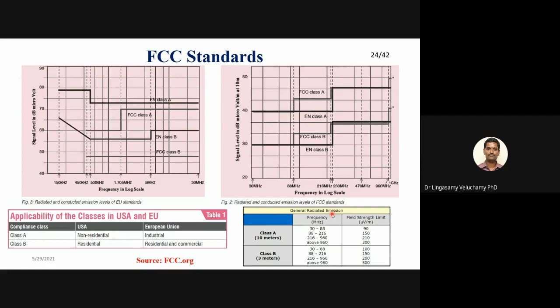Okay. So how do you have to measure? What tolerance limit? For example, for 30 to 80 megahertz, what is the tolerance limit? Similarly, for above 960 megahertz, what is the tolerance limit? All the limits will be specified. That's what I was telling. The standards will be dictating. So what is your device, what is the application of the device? Based on that, it will dictate how you have to measure, where you have to measure, what sort of test setup you have to follow, what sort of equipment you have to use, and what sort of limits your device has to comply with. Everything it will dictate. Okay.